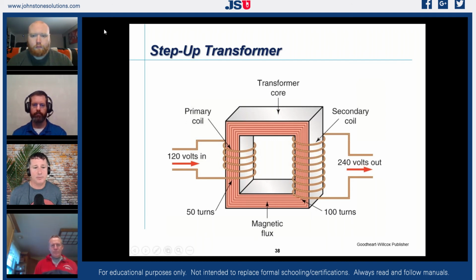If we think about why a transformer is going to fail—and I encourage you guys as technicians to try this—if I have a transformer fail, remember I have two separate windings there. Find out which winding failed. I'll guarantee you, if a transformer burns up, it burnt up because we had too much load, we tried pulling too much load on one winding or the other. It's typically our secondary winding. So the next time you have the opportunity to find a burnt-up transformer in the field, take that transformer, get your meter, put it on resistance, and take a look at your two windings.